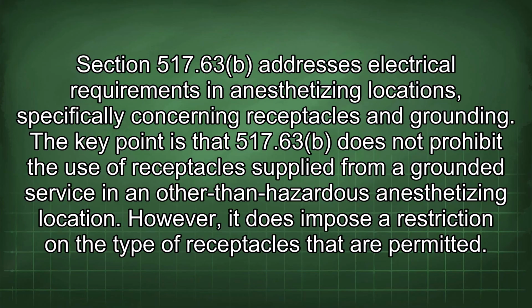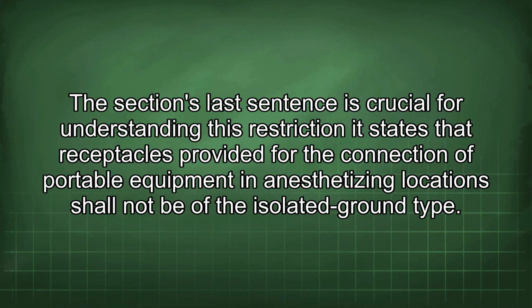517.63 addresses electrical requirements in anesthetizing locations, specifically concerning receptacles and grounding. The key point is that 517.63 does not prohibit the use of receptacles supplied from a grounded service in an other than hazardous anesthetizing location. However, it does impose a restriction on the type of receptacles that are permitted. The section's last sentence is crucial for understanding this restriction.